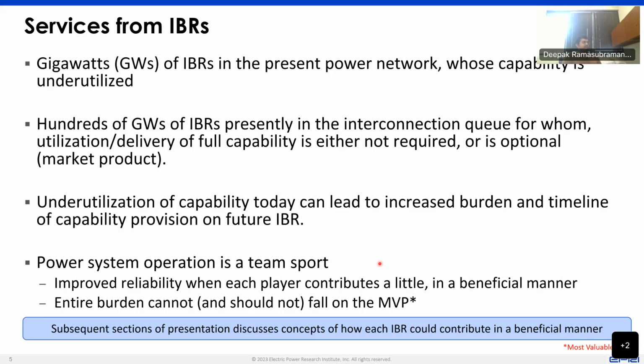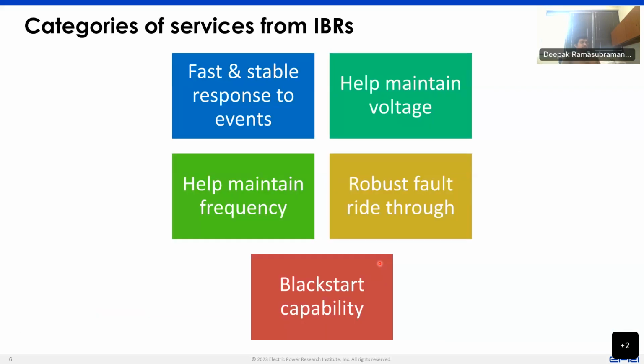So now if we categorize the services that we require from inverter-based resources, and here we're talking predominantly about interconnected power systems, maybe something like a large interconnection and so on. Some of it applies to small island power networks also, but the majority of it is an interconnection network. Then we want an inverter to respond in a fast and stable manner to events. We want it to help maintain voltage. We want it to help maintain frequency, and we want it to have robust fault ride-through.